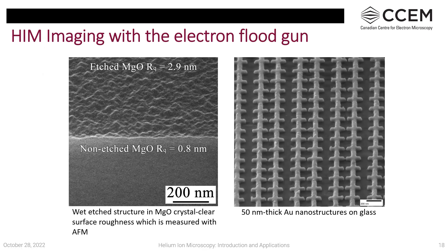More HIM imaging with the electron flood gun from my own samples: to the left are etched structures in MgO single crystal, an insulator with no material contrast — just surface topography. You can clearly see the surface roughness, measured at 2.9 nanometers with AFM compared to 0.8 nanometers for a smoother region. To the right, gold nanostructures fabricated on glass show clear surface details, which would be very difficult to image with SEM, especially for the MgO case.